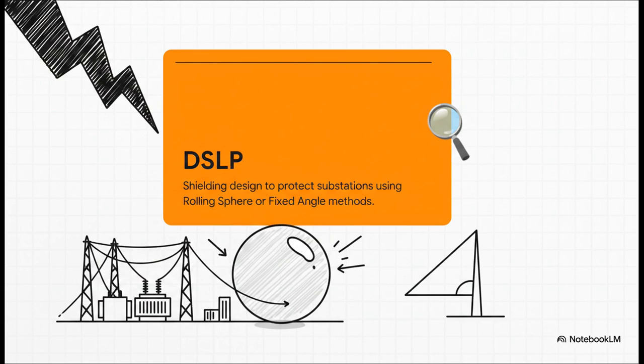Let's zero in on lightning protection for a second. You are going to master DSLP, direct stroke lightning protection. This means evaluating site-specific data to build shielding designs using either the fixed angle or the rolling sphere method.